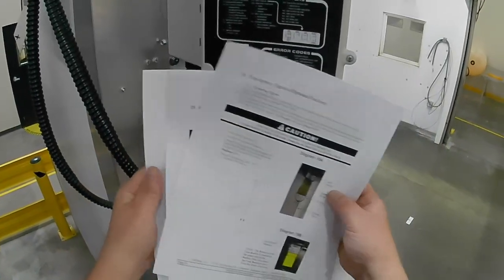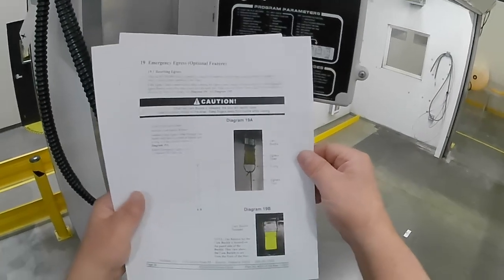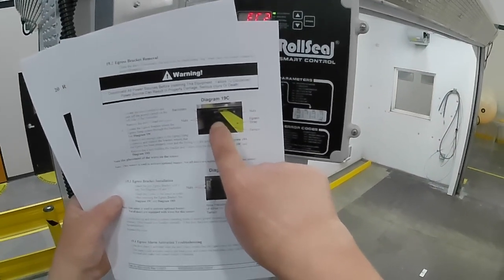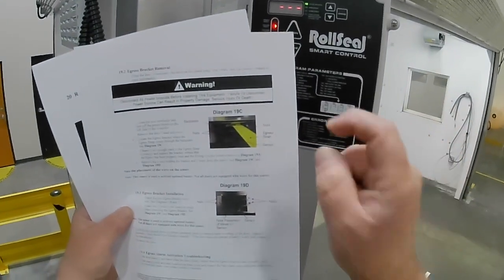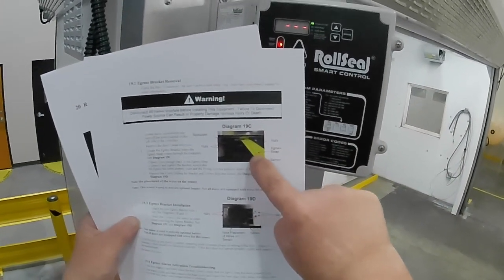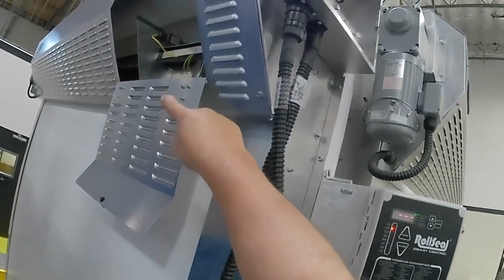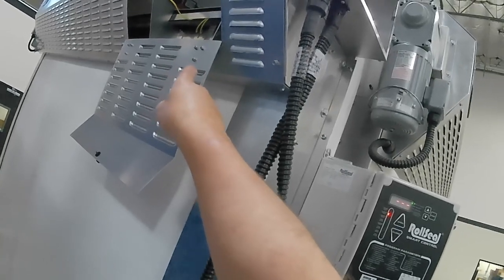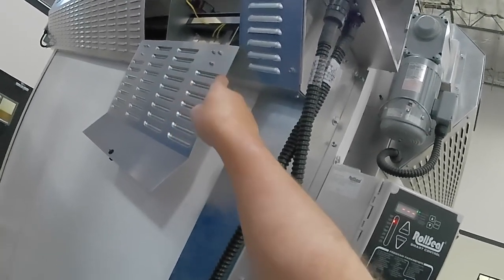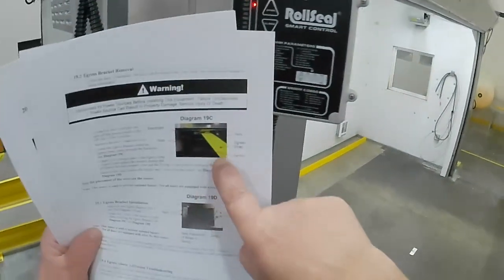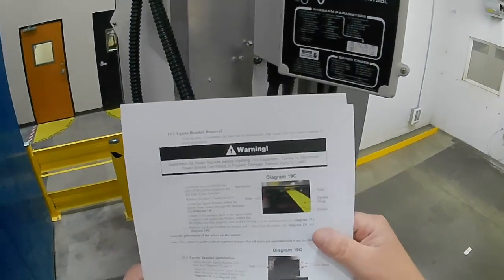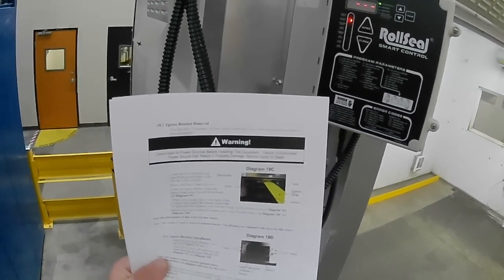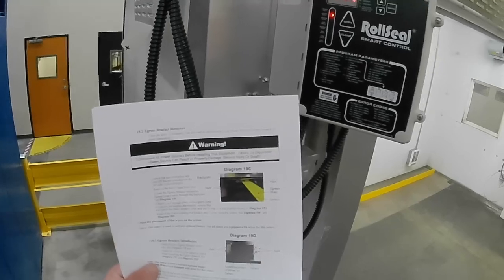I was reading into that because on one of these pages, it indicated that behind that curtain there is also a switch, which would make up the third switch that I've been looking for in this entire assembly here, boys. I only saw two switches when it originally said there should be three switches. So they basically translated that safety switch into the egress switch, and they didn't tell you. That's why I tell you, the troubleshooting guide is just a guide, for the quick low-hanging fruit, boys.